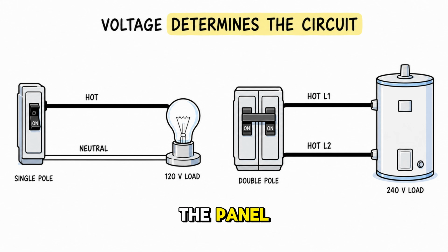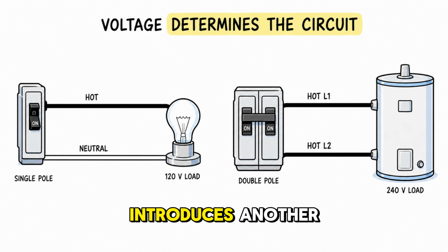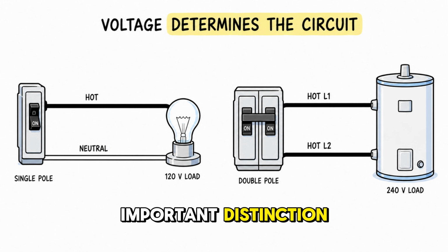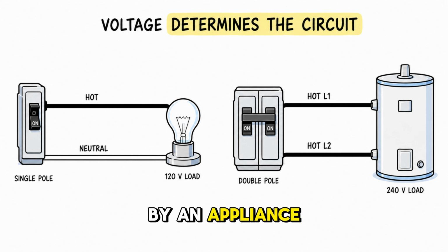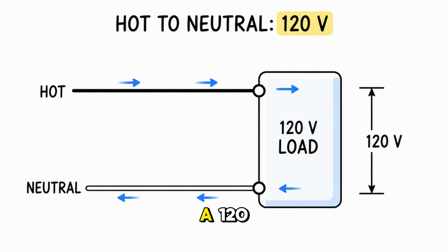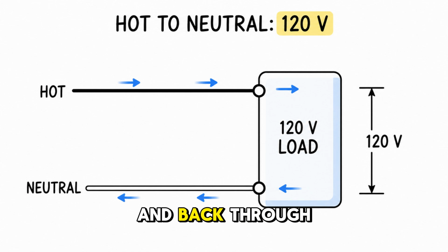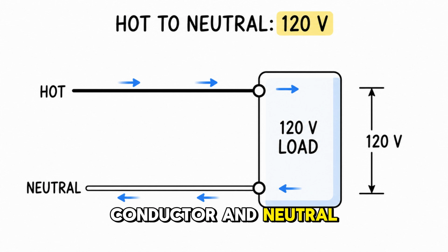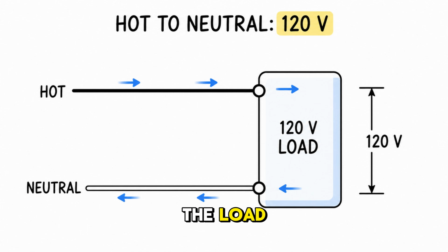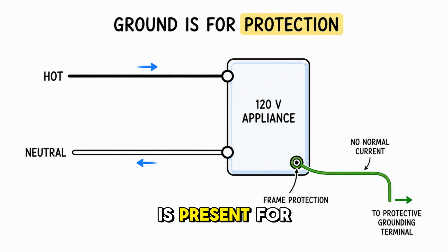But understanding how the panel produces those voltages introduces another important distinction. The voltage needed by an appliance determines both the breaker it uses and the conductors required to complete its circuit. A 120-volt appliance needs a path from one hot conductor through the appliance and back through neutral. The voltage between that hot conductor and neutral pushes current through the load. The equipment grounding conductor is present for protection, but it is not intended to carry normal operating current.